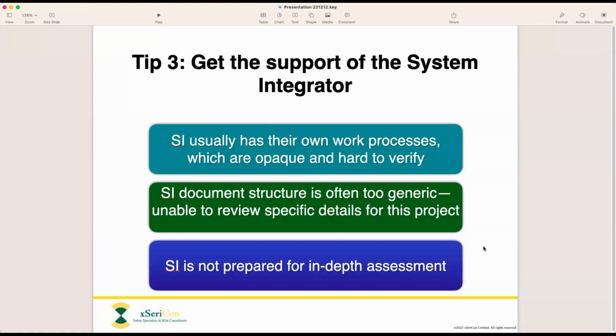Now, very often when we open up the specification provided by the system integrator, we'll see a statement such as, you could do this, or you may do that, or here are your options for what to do when a fault is detected by diagnostics. But it doesn't say what the system actually will do. It just says, what are the options? And that's not enough.